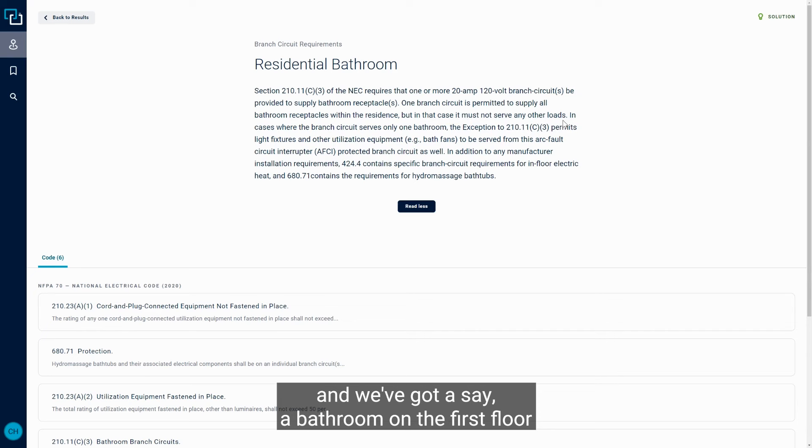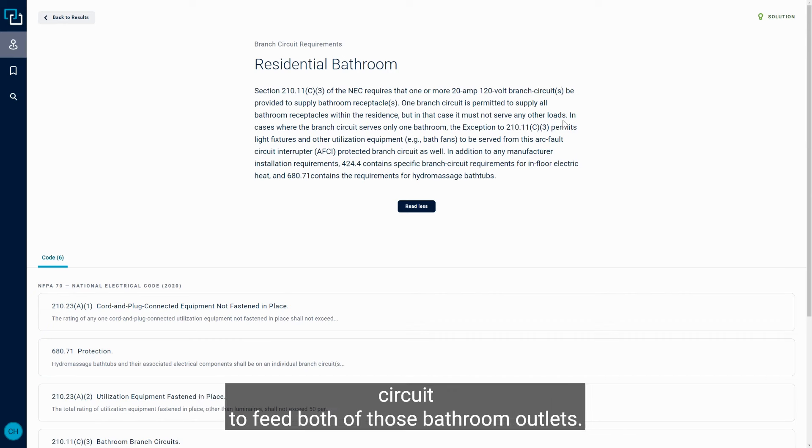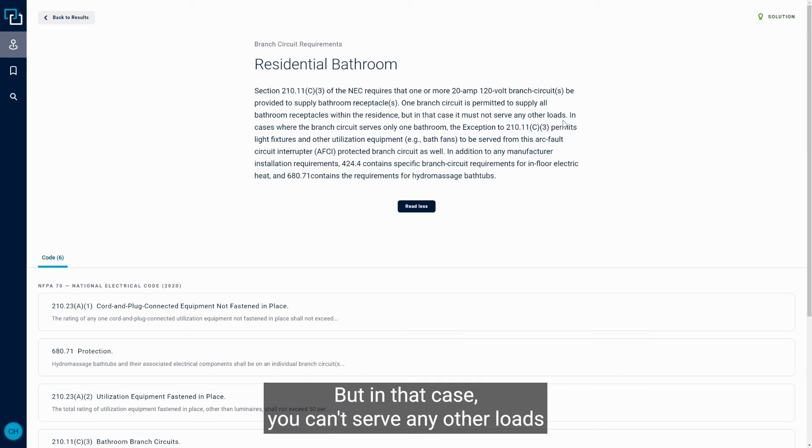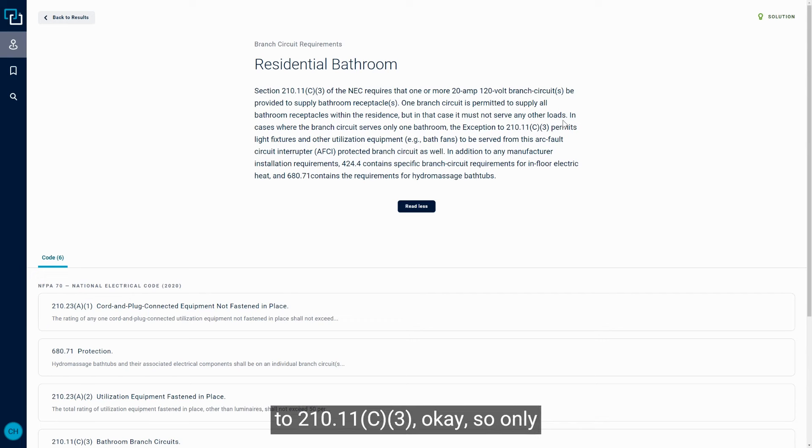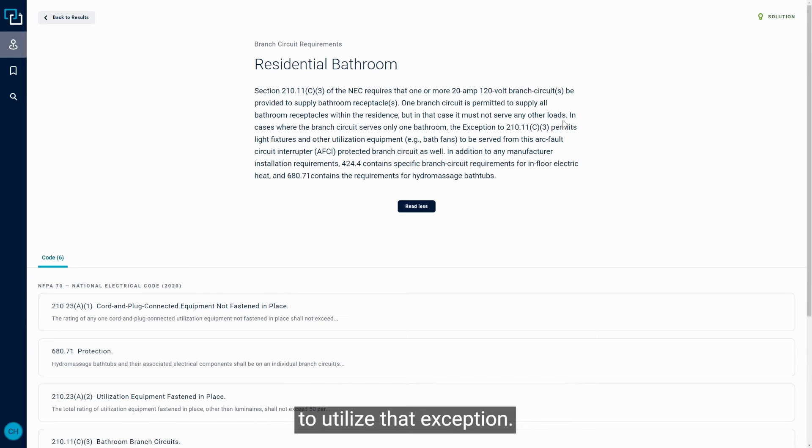So if we've got that one circuit we're talking about, and we've got a bathroom on the first floor and a bathroom on the second floor, and we're going to use that one 20 amp branch circuit to feed both of those bathroom outlets, that's fine. But in that case, you can't serve any other loads that were listed in that exception to 210.11.C.3. Okay, so only if that circuit feeds just a single bathroom is it permitted to utilize that exception.